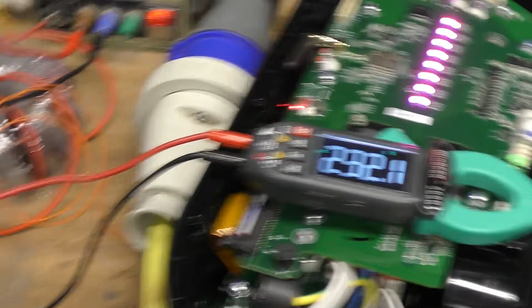And I've just checked that it does also trip if the car's not connected, which of course is reasonable. It could indicate, say, cable damage or something, if you're getting current flowing through this earth when there's nothing connected. Another possible symptom of a PEN fault is reduced supply voltage. So I'm just going to see what happens if we reduce our mains voltage. There is an explicit alarm that you can set in the app to make it trip for over and under voltage, but let's just see what it does on the default settings.